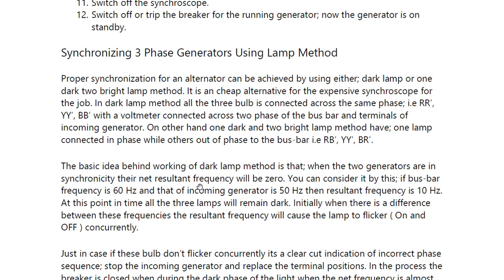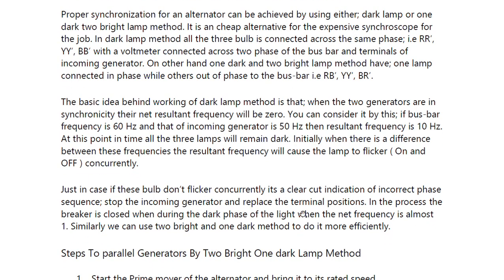The basic idea behind the dark lamp method is that when the two generators are in synchronicity, their net resultant frequency will be zero. For example, if the bus bar frequency is 60 Hz and the incoming generator is 50 Hz, the resultant frequency is 10 Hz. When there is a difference in frequency, the resultant frequency will cause the lamps to flicker on and off concurrently. If the bulbs don't flicker at all, it is a clear indication of incorrect phase sequence — stop the incoming generator and swap the terminal positions. The breaker is closed during the dark phase of the lights when the net frequency is almost zero.